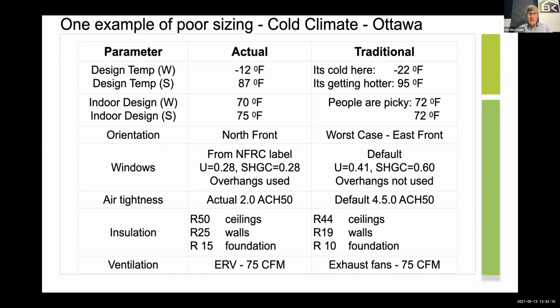And our indoor design temperatures, you could quibble with this one. Let's be really clear. A heat loss, heat gain is done assuming 70 degrees, 21 degrees Celsius, 70 degrees Fahrenheit. Some have changed it to 22 Celsius, so 72, but nonetheless, 70 degrees. And the design cooling day, the inside design is 75. And many of you will say, my homeowners want it cooler than that. Well, then I guess you should design for cooler than that. But it is designed for that.